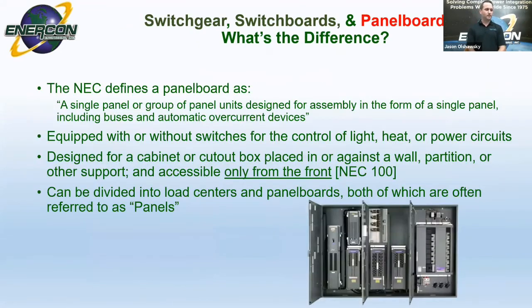Next slide, please, Sean. So the NEC defines a panel board as a single panel or a group of panels designed for assembly in the form of a single panel, including buses and automatic overcurrent devices. These can be equipped with or without switches for the control of light, heating, and power circuits, designed for a cabinet or cutout box placed in or against a wall, partition or other support, and accessible only from the front. These can be divided into load centers and panel boards, both of which are often referred to as panels. In this example, we have several different panel boards located within one enclosure. We're grouping those together for ease of access and less cabling, just putting them all in one container.